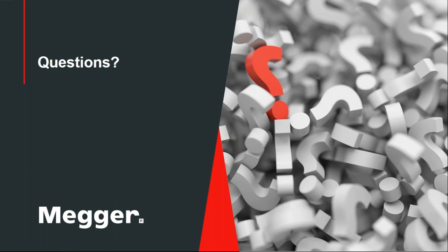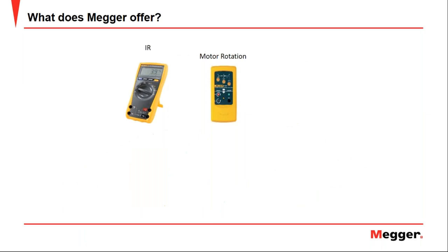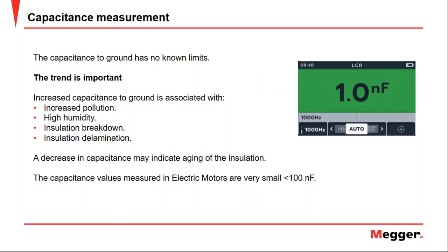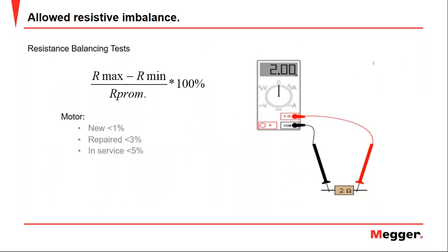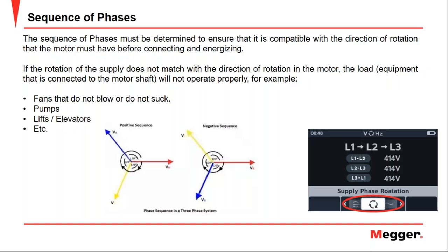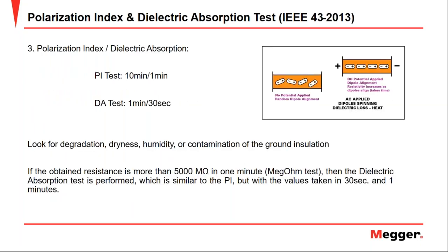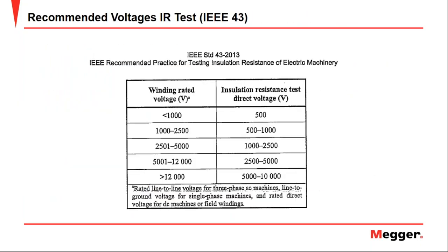Okay, so the first question is, would you test a 690 volt AC motor with 500 or 1000 volt DC? Is there an explanation on why low voltage motors are tested with voltages over their nominal value, but in high voltage motors, the IEEE asks to use less than nominal voltages for testing? Yes, let me go to the table to show. Here we are.